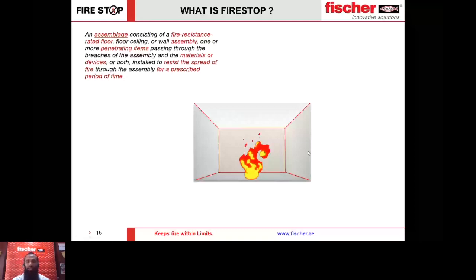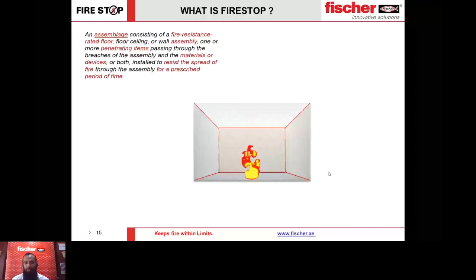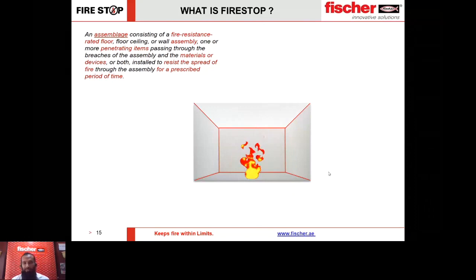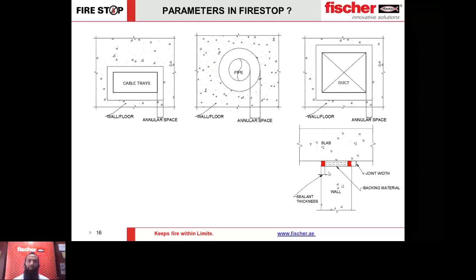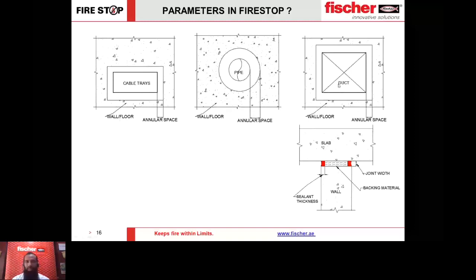Now we introduce the concept of fire stop. Fire stop is basically reinstating the rating of the fire barrier after it has been broken by some action. You have joints, MEP services penetrating the barrier, and you do a treatment on that — that is what is called fire stopping. Fire stopping would be required in fire barriers only, where the fire barrier has been breached by introducing some kind of service such as cable trays, pipes, or ducts.